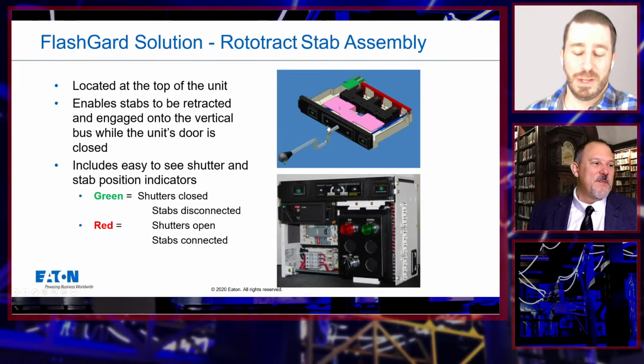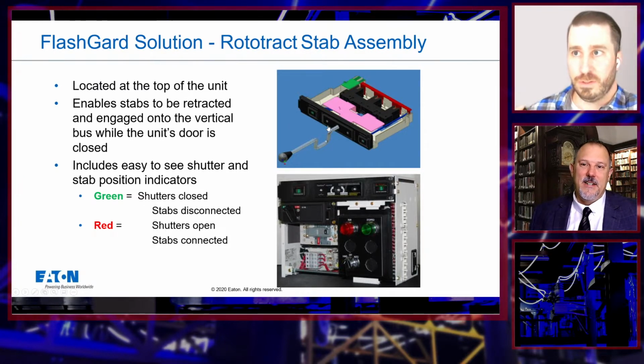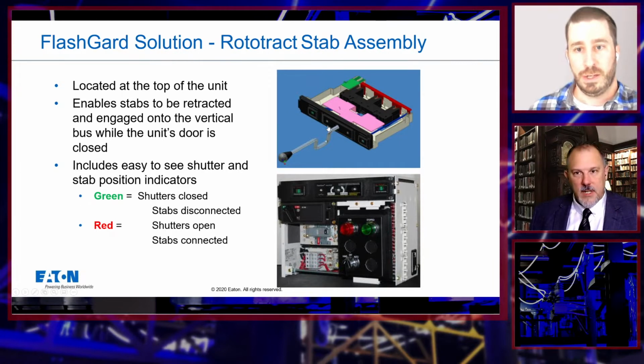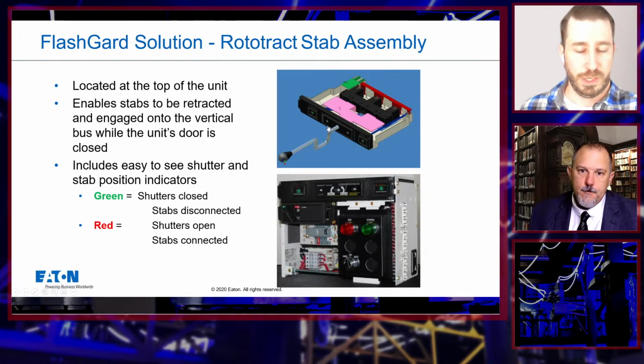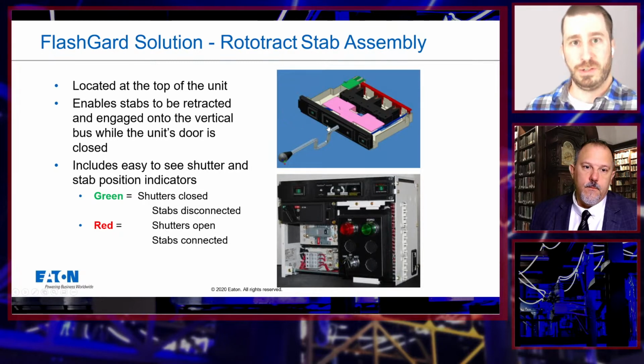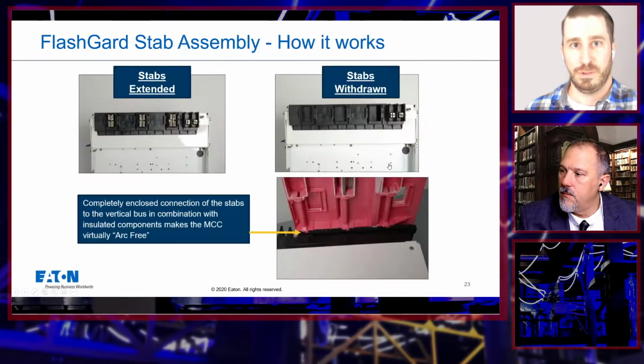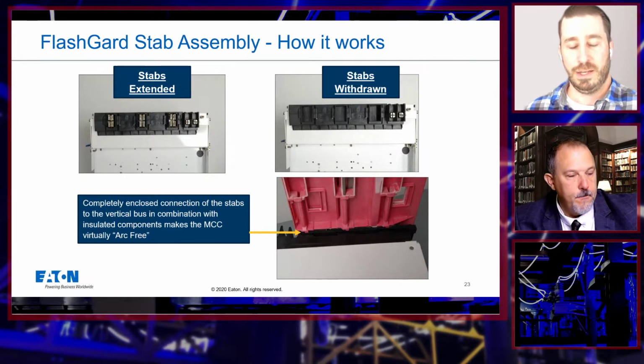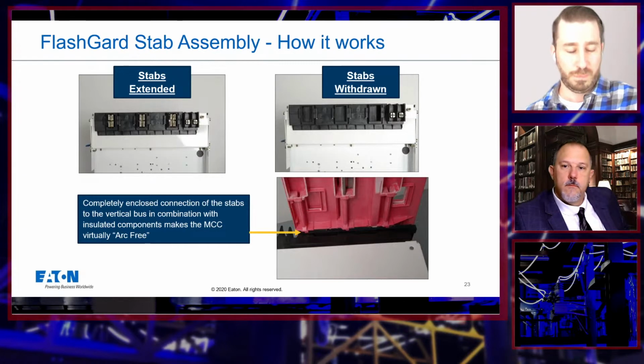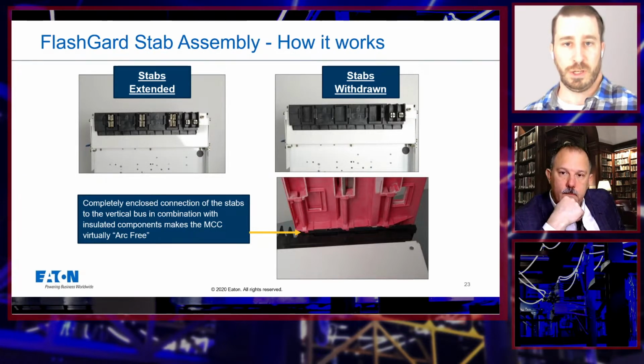To be honest, there's an area even in the choice - we have starters and drives and protective devices. The conditions in which somebody gets in are often related to a troubleshooting scenario. If you think about the choice of motor protection, where you've got relays with localized HMIs that allow an operator to see what's occurred, whether from a trip unit, an overload, or a drive, you're giving them the ability to interrogate what's going on without having to get into the equipment. You hear time and time again, we're trying to do things without having to get into the compartments.